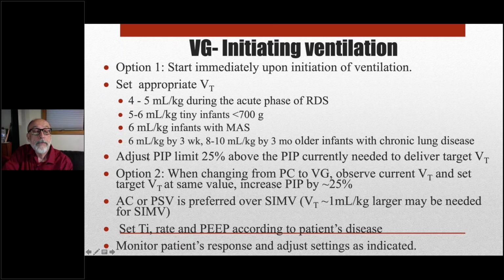Then we need to set the pressure limit. The device will adjust pressure up and down up to a limit that you set. That limit needs to be close enough to the actual pressure to give you an alarm if conditions have changed and the ventilator is not able to reach the tidal volume that you have asked for at the pressure limit that you selected. All right.